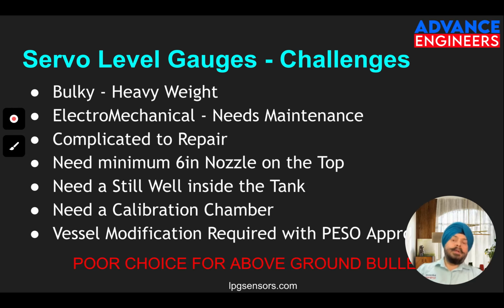That is the issue. Next, and the biggest point over here, is it needs a minimum 6 inch nozzle on the top, because that is mandatory, because you need to create a float which can actually float on the LPG. So the float design has to be such that it floats on the LPG. Traditionally we have been using a minimum 6 inch float. Nowadays we have brought the size down from 6 inches to 4.5 inches, but still the float is quite big because it has to float. So we create a surface area so that it floats on the LPG, because LPG density is way too low.